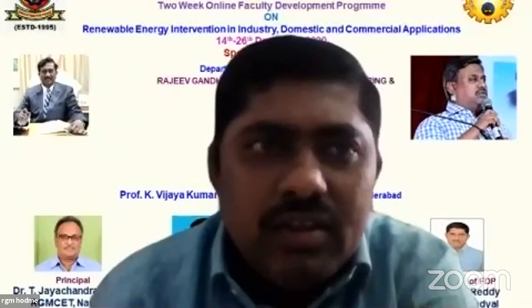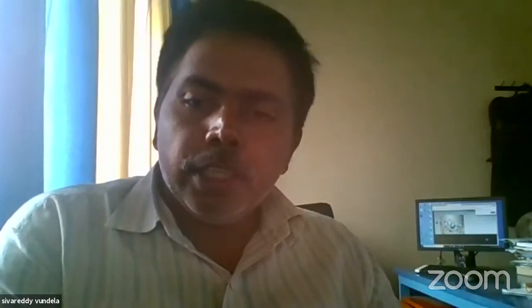There are doubts from Siddharth sir and Shankar R. Doboji sir, regarding the economic viability of vapor absorption refrigeration systems. Yes, more than 30 tons refrigeration capacity, vapor absorption systems are economically viable. Less than 30 tons it is not economically viable. This applies across 5 tons, 10 tons, 15 tons, 30 tons, up to more than 150 tons.